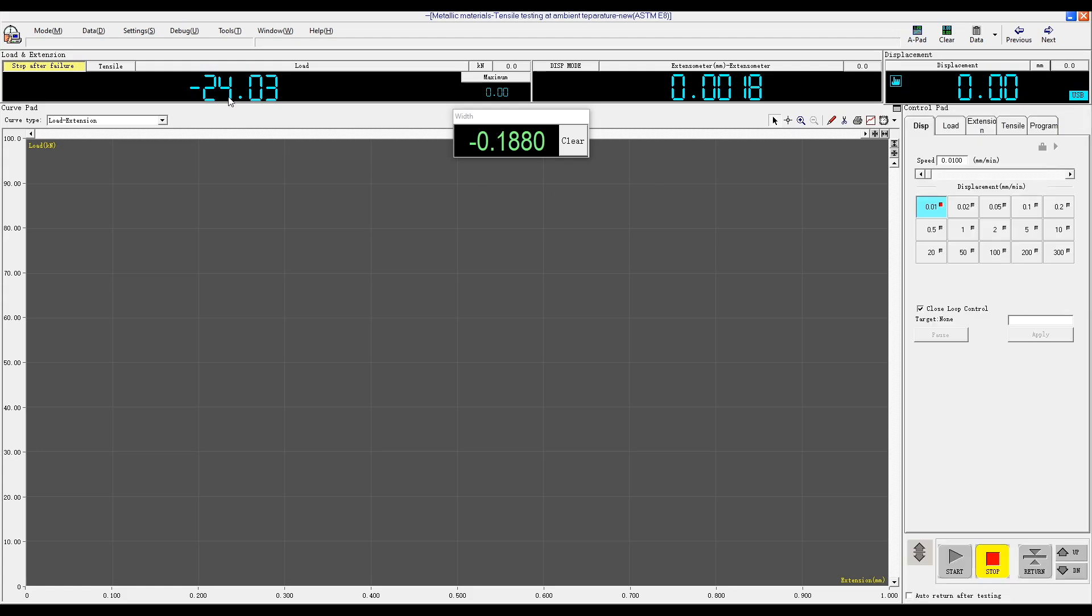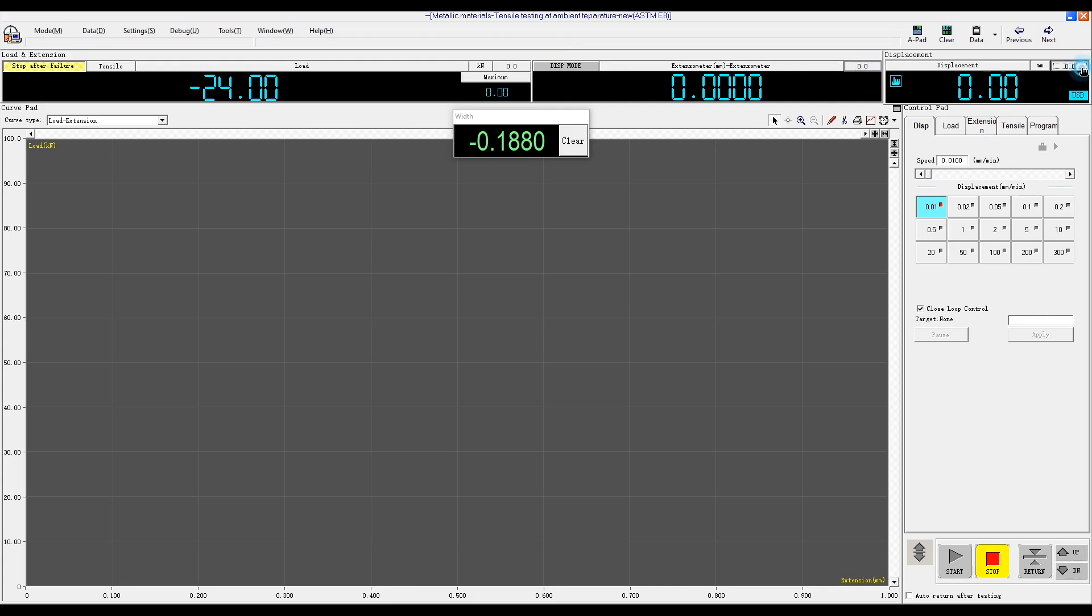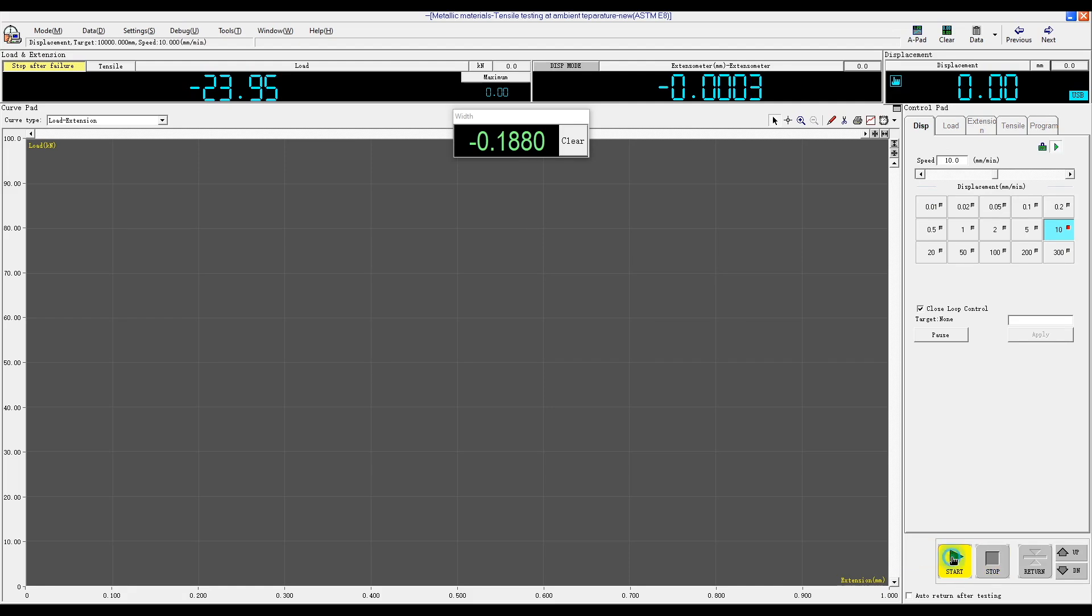The extensometer display mode should be selected in gray color. The test should indicate zero extension and zero displacement. For the control mode, you can choose from tabs including displacement control, load control, extension, and tensile program. Typically, we start with displacement control. Then select the speed, for example, 10 millimeters per minute, and click Start Test.